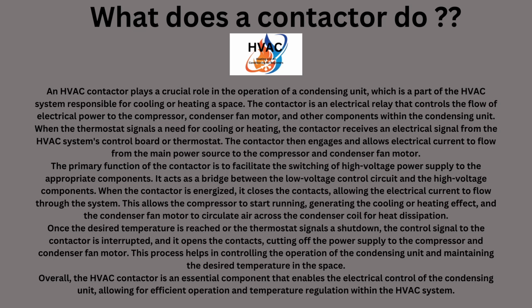Once the desired temperature is reached, the thermostat signal shuts down. The control signal to the contactor is interrupted and it opens the contacts, cutting off the power supplied to the compressor, the condenser, and the fan motor. This process helps control the operation of the condensing unit and maintain the desired temperature in the space. Overall, the HVAC contactor is a central component that enables the electrical control for the condensing unit, allowing for efficient operation and temperature regulation within the HVAC system.